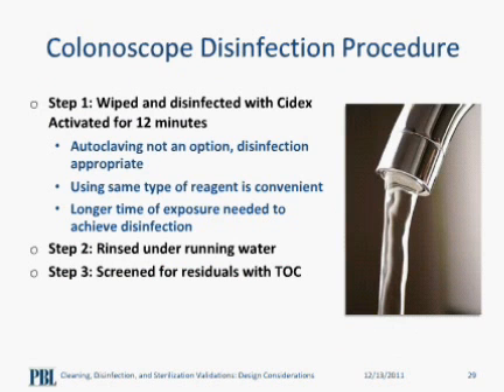Since this is a semi-critical device, it needs to be disinfected or at least close to sterile. High temperature is not an option for this particular device. Hence, the only way to make it safe for reuse is to subject the device to a disinfection process after the cleaning. The immersible part was soaked in Cidex for 12 minutes, which is the time indicated in the manufacturer's manual of instructions. However, the exposure time varies from one disinfectant to another. Then after soaking, thorough rinsing was performed to remove chemical residuals.